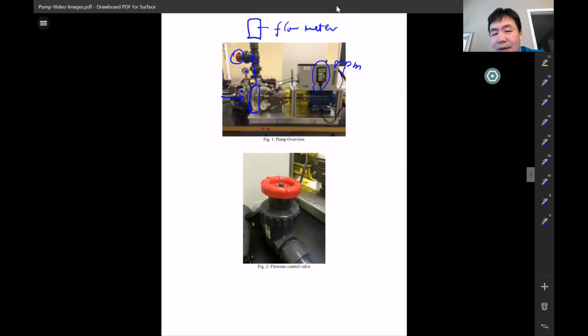So in this lab, we are going to simulate two pumps, one slightly different to the other one. We try to simulate it, but the goal is still to measure two pump curves for the two similar pumps. It's very easy to simulate two different pumps. Here you actually have the same pump. You can adjust the RPM. The first RPM is maybe 90%. The second RPM is 60% for the speed. So then these are the two similar pumps. They should satisfy the affinity law for the relationship.